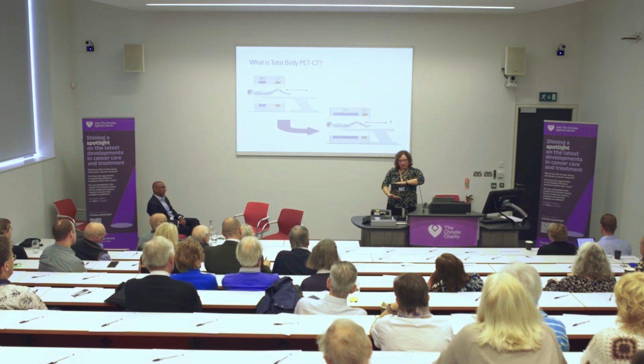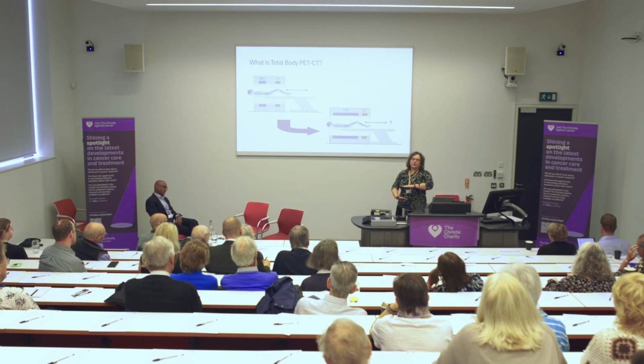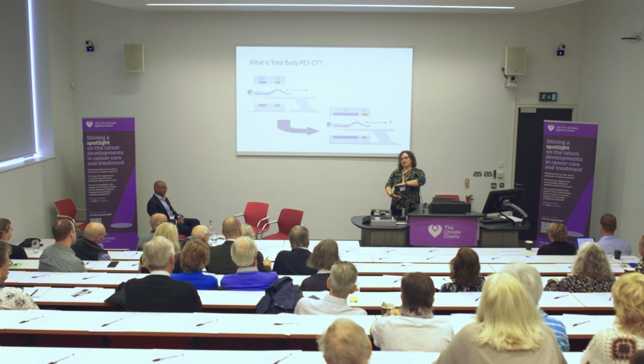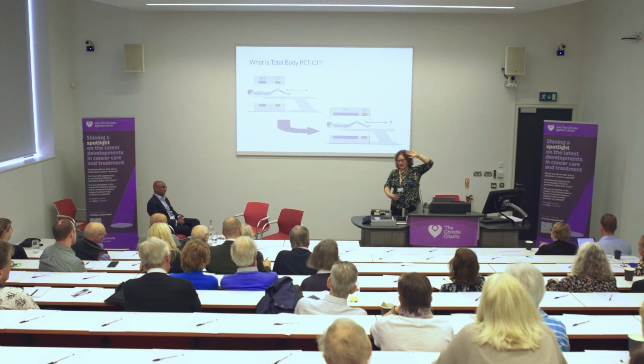It's also, if you imagine that the patient is giving out radiation in all directions, if you could just imagine a light bulb roughly where your belly button is, go with it for a second. And you've got all that radiation shining out in all directions. If you have a PET scan that's about that long, you're only going to collect in one go the light that's coming out from that section. If you cover all of your body in a PET detector, you're picking up the radiation from this point at the PET detector that's here and here and here and here and all the way around you as well. And that means that the longer you make a PET detector, the more sensitive it is. And if you make it much, much longer, it gets incredibly more sensitive compared to a standard scanner. And that means we can scan really quick, as well as scan everything all at once.